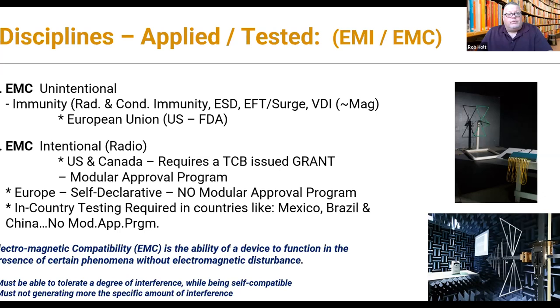In Europe, it's self-declarative, but there is no modular approval program — you don't get a grant or type approval certificate in Europe. It's on the honor system. So you need to test that module in your device and prove it's passing. There are other countries that require in-country testing: Mexico, Brazil, and China — they also do not have a modular approval program.